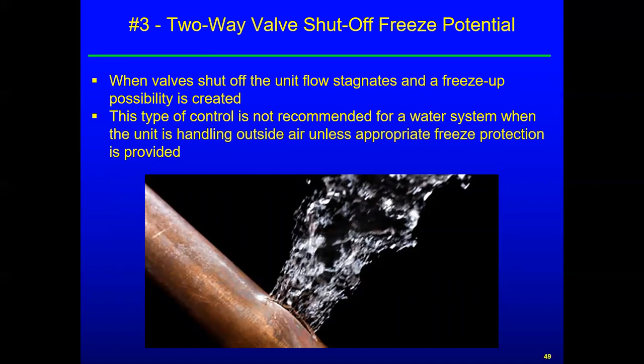Okay, well, what about freeze? When you have a coil, we're always concerned about freezing the coil, and the coil or a pipe up around the coil bursting, flooding the unit. That's just a bad day all over the place for everybody. So if we're going to use a shutoff valve on a coil, then there's no flow through the coil, and a dead coil is much more likely to freeze than one that has some kind of flow through it. So the freeze-up possibility is created or really enhanced.